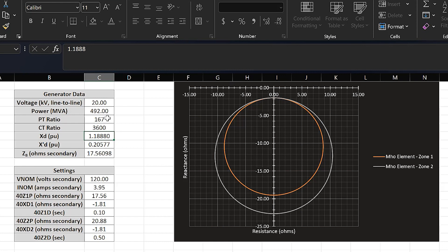We need to convert these reactances from per unit to secondary ohms, because the relay uses secondary voltage and current and needs the secondary impedance, not the per-unit impedance. We convert using the PT and CT ratios for the specific scheme. The spreadsheet converts everything to secondary ohms, which you can then enter directly into the settings file. The spreadsheet is available for download using the link in the description.